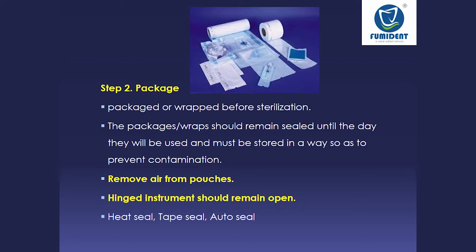Then again, you have to remove whatever air is present inside the pouch so that the steam penetration will be proper. If you are using a sealing machine for sealing these pouches, you have to make sure that your sealing machine is of medical grade packaging. This is because many of us use a simple machine of food grade quality, and because of that there may be a micro gap or micro leakage in the packaging.